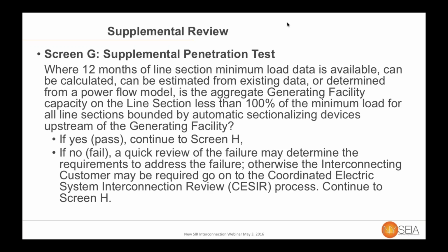The first screen is the one that generally is the most focused on. It's the supplemental penetration test. So as mentioned, the 15% is generally a very conservative estimate, and therefore the new screen is 100% of the minimum load. So if the minimum load is known from data, if it can be calculated, if it can be estimated from existing data, or if it can be modeled from a power flow model, knowing the class of customers connected to that line, then you can pass this screen by moving up to as much as 100% of the minimum load. It's a more sensitive screen than that kind of blanket 15%.